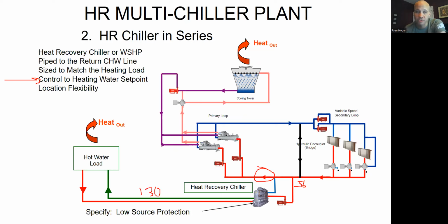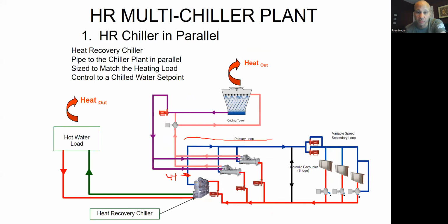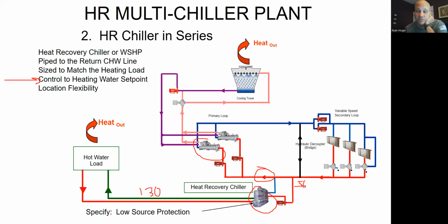This is probably a slightly more preferred way to do this for most people's applications, especially if this chiller is small relative to these chillers. If they're pretty close to being equal in size, then the other way is probably going to work out a little bit better. But if this is like a little tiny pony chiller and it's only doing a couple hundred tons, let's say 100 tons of cooling on a plant that does 2,000, this is probably a better way to do it.